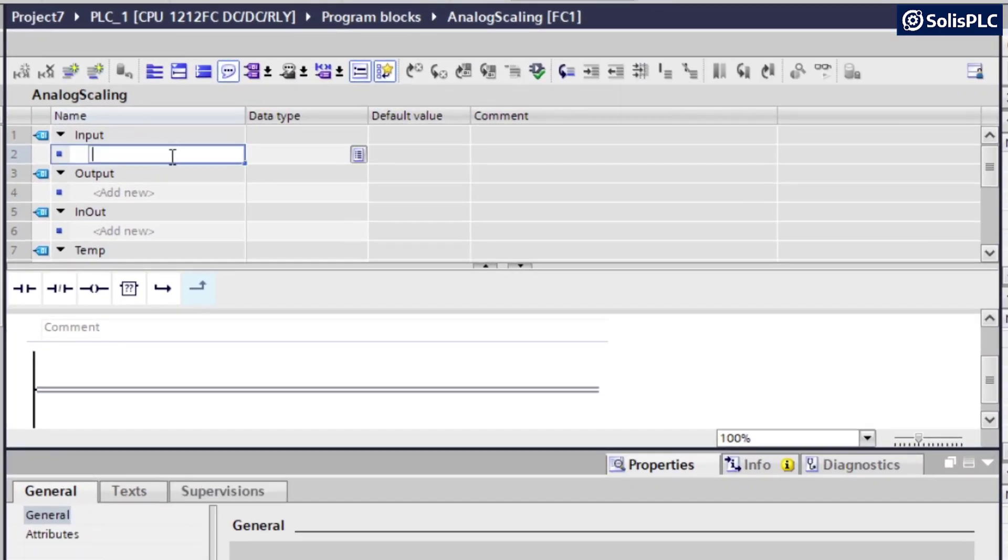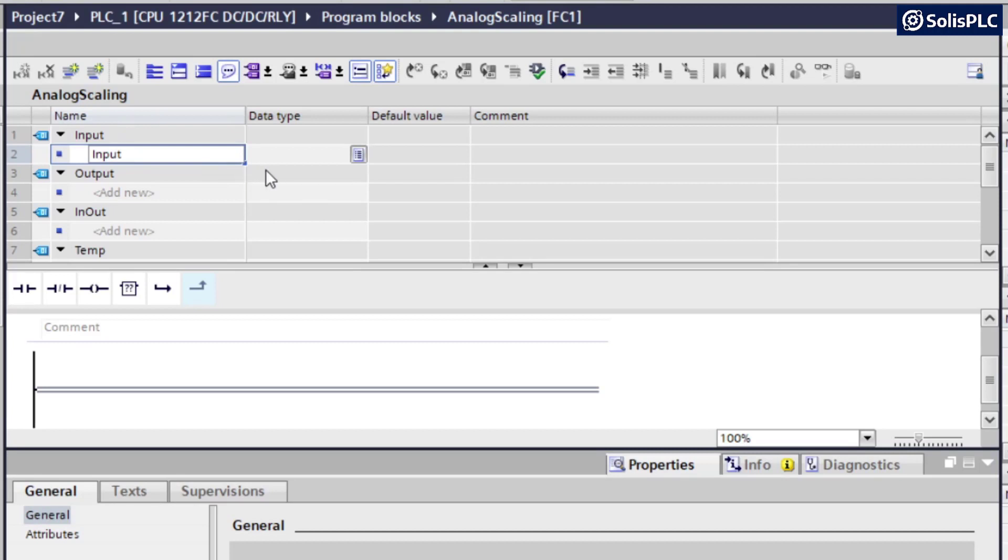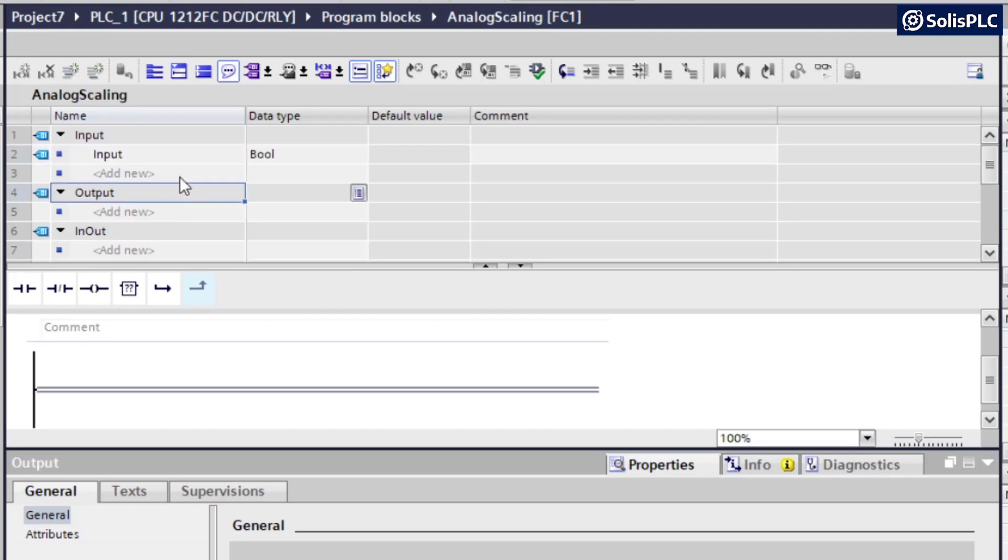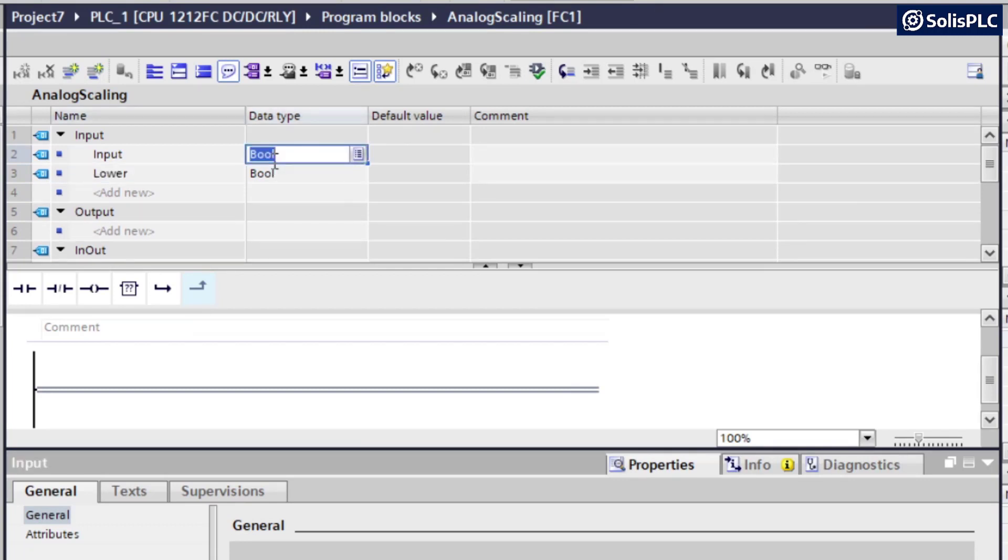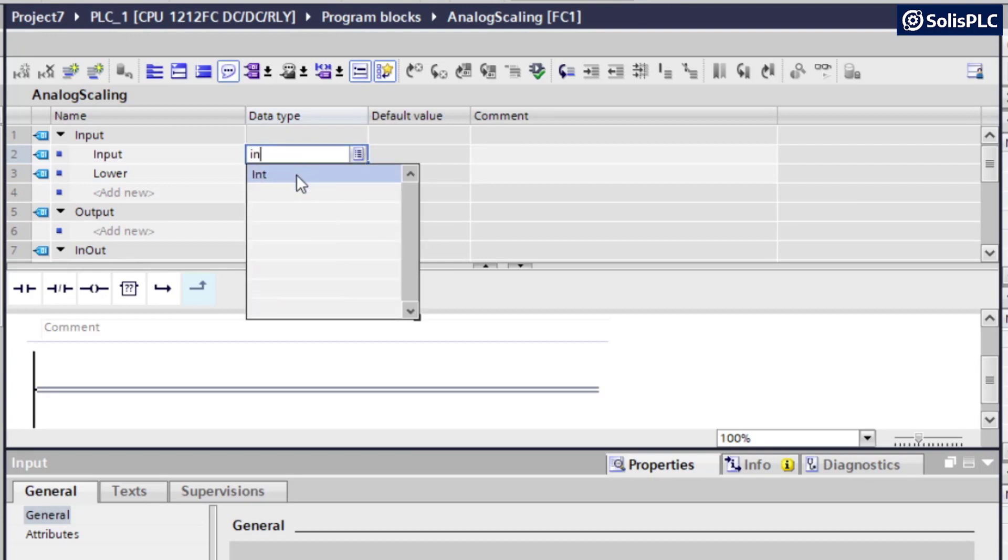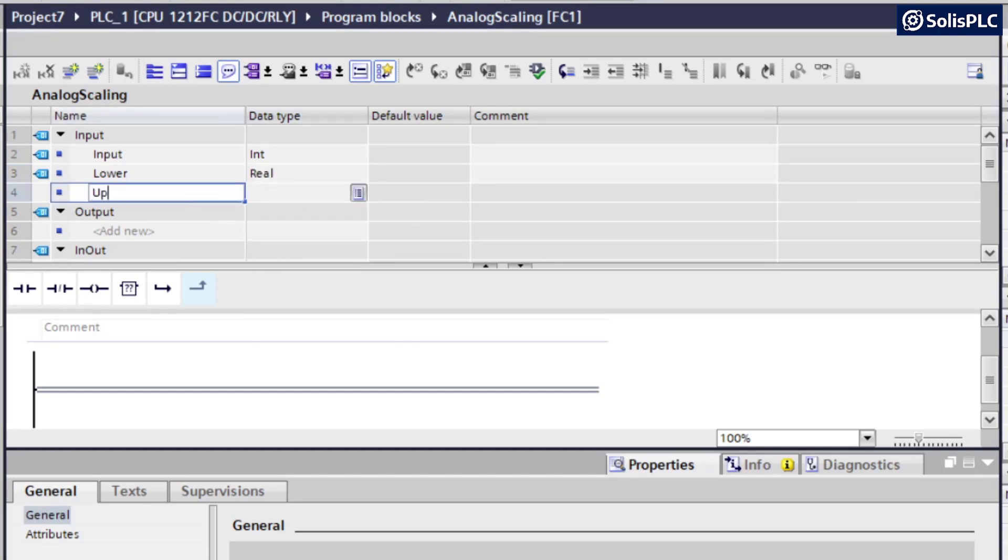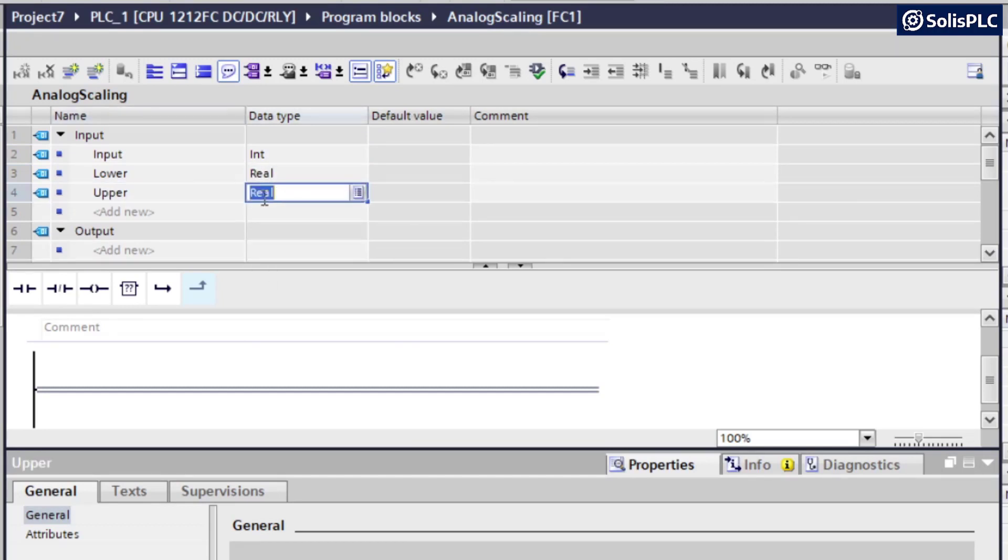So before we build our instruction, we can specify several inputs and outputs that we're going to provide. So on the input side, the first one is going to be the input, which is going to be the unscaled value that we expect to get into our function. We're then going to select the lower and upper bounds for our specific range. So this is going to be lower. And we do have to change the type. So the input is going to come in as an integer. So I'm going to specify that. The lower bound can be a real.